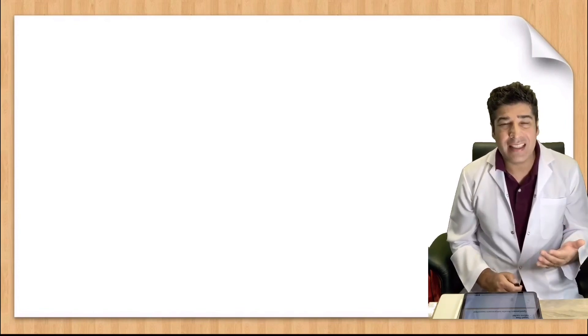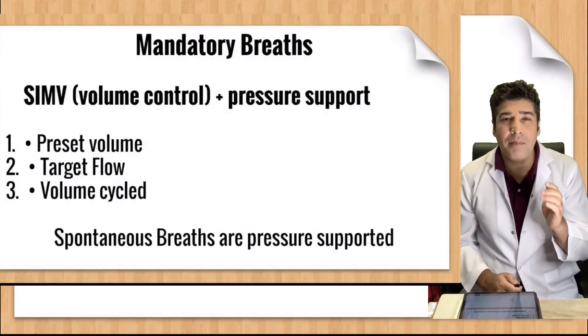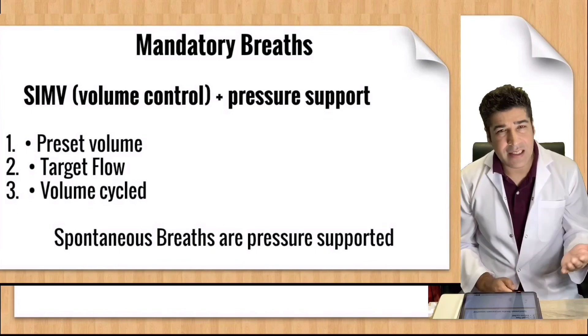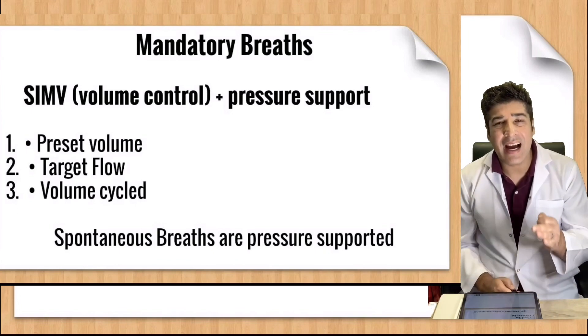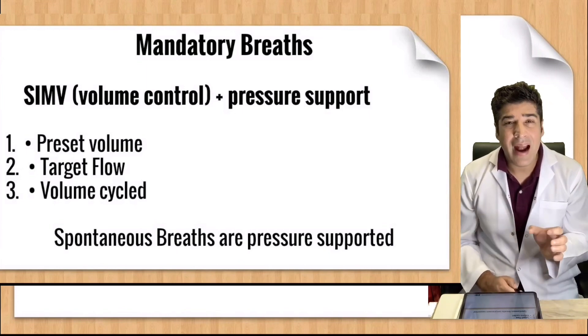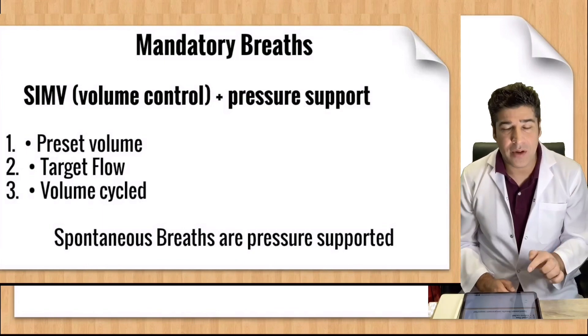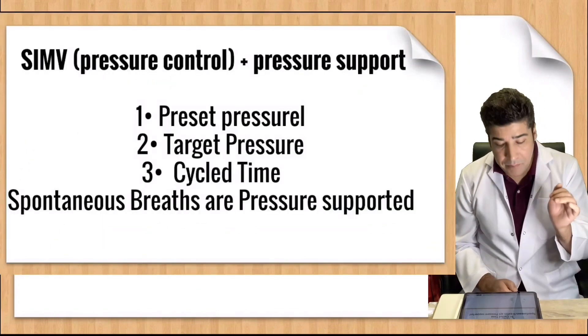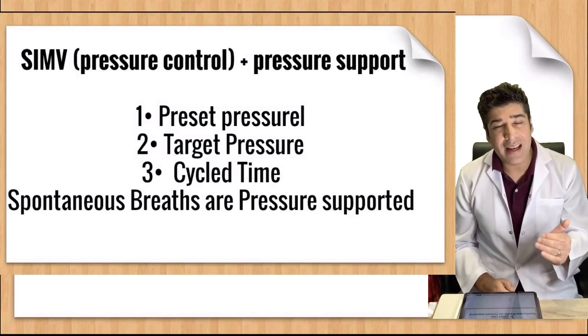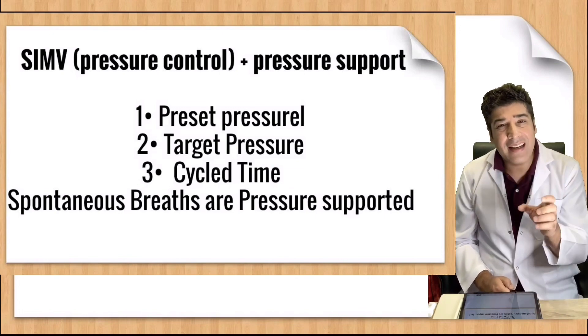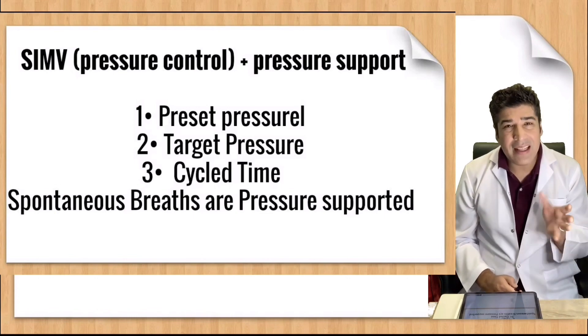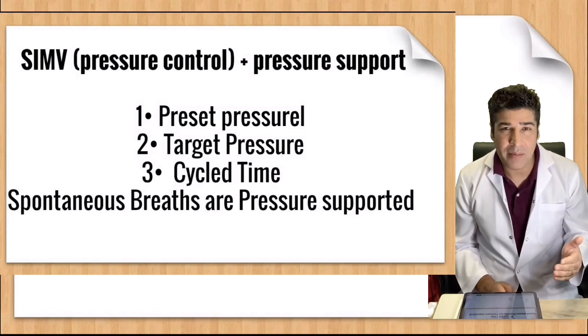In SIMV volume control plus pressure support, volume is preset, the target is flow, and the cycle is either volume or time. The spontaneous breaths are pressure supported. In SIMV pressure control plus pressure support, pressure is preset, the target is pressure, and it is time cycled. The spontaneous breaths are also pressure supported breaths.